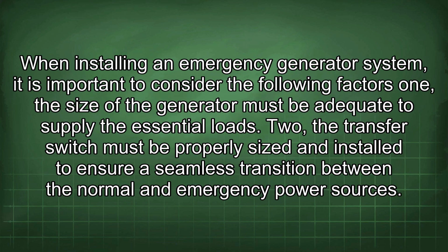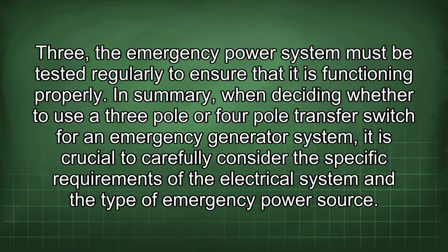When installing an emergency generator system, it is important to consider the following factors. 1. The size of the generator must be adequate to supply the essential loads. 2. The transfer switch must be properly sized and installed to ensure a seamless transition between the normal and emergency power sources. 3. The emergency power system must be tested regularly to ensure that it is functioning properly.